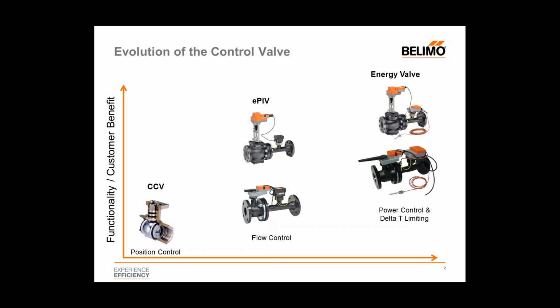But with power control, we have the ability to correlate that DDC signal directly to a BTU output. For some specific applications, if they want to control to a specific BTU, they can set their DDC signal and it will correlate directly to that BTU output and modulate to maintain that BTU. It also has what's called Delta T Manager, which provides a delta T limiting function. We're going to talk a little bit more about that later, but basically what that addresses is what's known very well in the industry as low delta T syndrome.